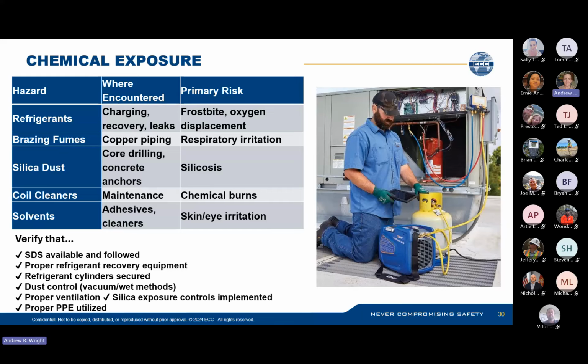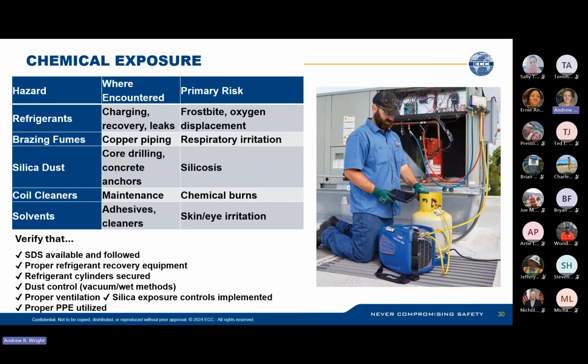You're going to verify that the SDS is available and followed, that proper refrigerant recovery equipment is in place, and that your cylinders are secured. A lot of times I see these workers let their tanks just roll around on the ground. So make sure that they're secured with the caps on. Dust control, vacuum, wet methods for silica, ventilation, and then your proper PPE. All right.